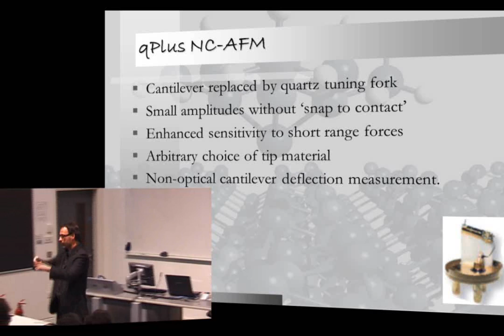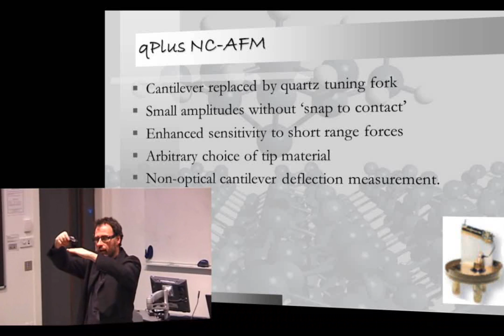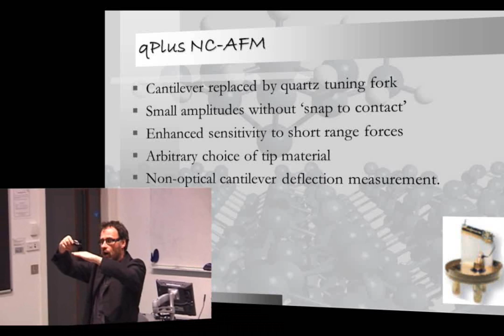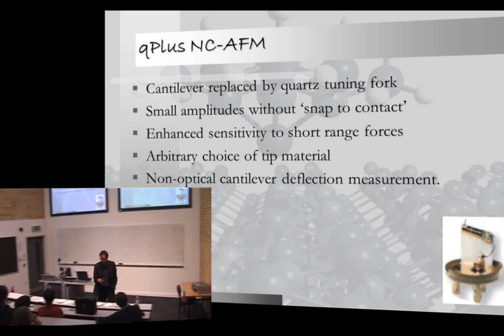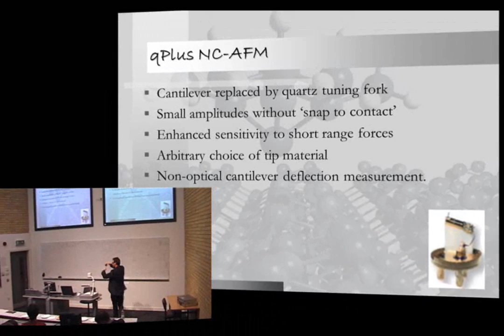What can happen with soft cantilevers like silicon is that because they're so soft, I mean the spring constant is low, when you bring them into the surface and you try to oscillate them above the surface, the interaction with the surface can exceed the stiffness of the cantilever, and it can jump in to contact, which is exactly what you don't want. So the great thing about tuning forks, because they're so stiff, is you can have a very low oscillation amplitude.